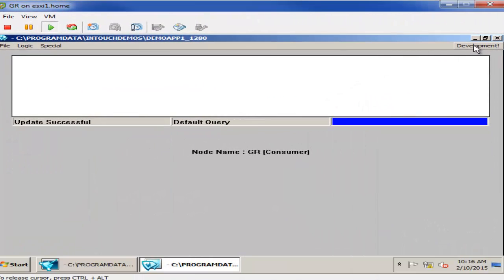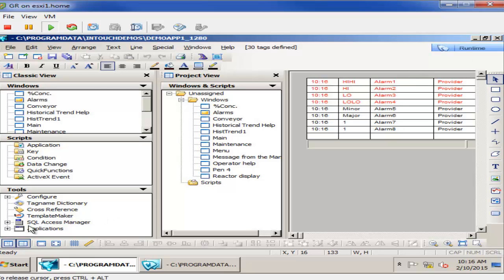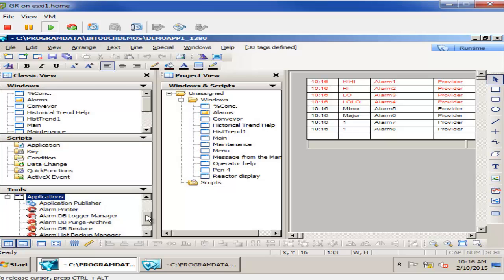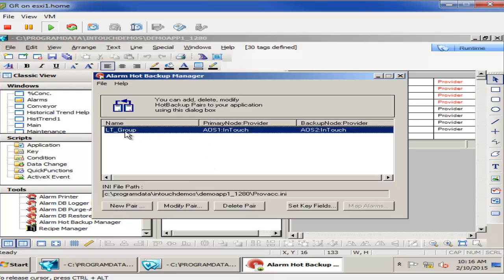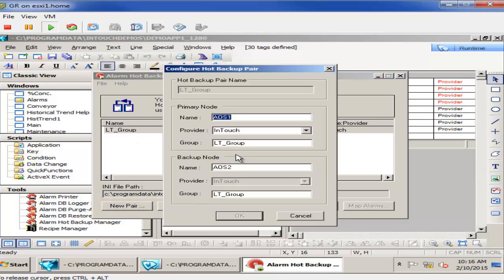The configuration for the Alarm Hot Backup Manager is quite simple. We go into InTouch under the classic view and configure the Alarm Hot Backup Manager by double-clicking. I've already added a pair in here, but yours will be empty. So you'll come in and select New Pair. That'll bring you to a screen where you can specify what the primary node and the backup node is, what the provider is, and what the group name to synchronize between the two.